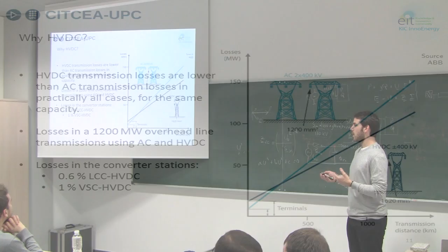The AC losses are even higher for shorter distances, around 400 or 250 kilometers or so. The losses in converter stations are around 0.6 to 1%. They are getting better, but going from 1% to 0.5% losses on a gigawatt means a lot of energy saved, so it's really important.